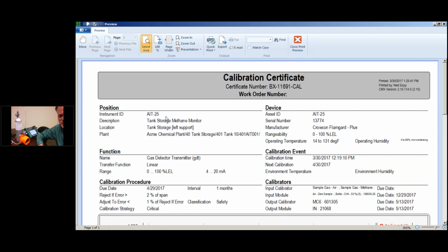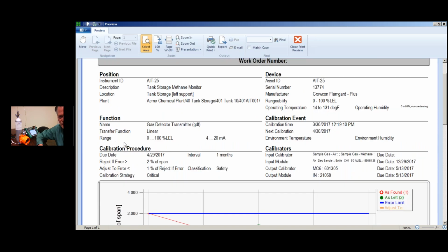So here I'm measuring a methane monitor in some kind of tank storage area. It's a Crowcon FlamGard Plus unit. The range is 0 to 100%. But here's my sample gas. I used air and methane. So air is obviously air. And then I had this lot number bottle for the methane. And then my milliamps was measured by the MC6.